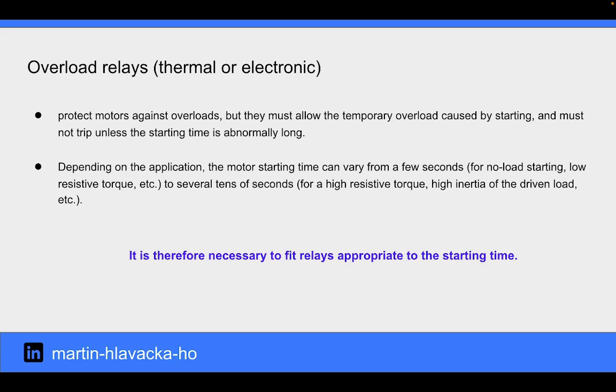Overload relays protect motors against overloads, but they must allow the temporary overload caused by starting and must not trip unless the starting time is abnormally long. Depending on the application, the motor starting time can vary from a few seconds to several tens of seconds. It is therefore necessary to choose relays appropriate to the starting time.